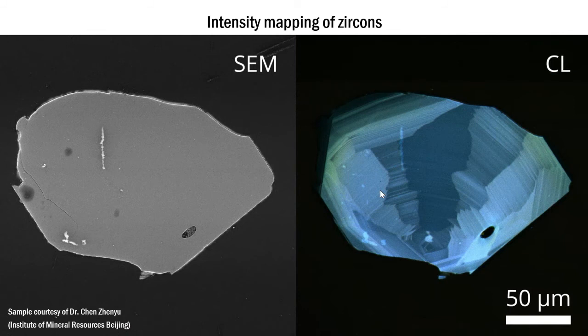Now, when we come to the current, we used 500 picoamps for this image. You could use a higher current, which would make the imaging faster, but we see that it may result in charging. So you wouldn't be able to acquire a good quality image. Now, as I mentioned, in addition to the beam conditions, the CL detector parameters also need to be optimized. The pixel dwell time used here was 40 microseconds, so the electron beam was exposing every pixel for 40 microseconds. A higher dwell time would result in better signal to noise ratio, that's true, but it would also take longer to acquire the image. So it's important to realize that there's a trade-off that's been achieved here. The parameters have been selected to give a high quality image of this sample.